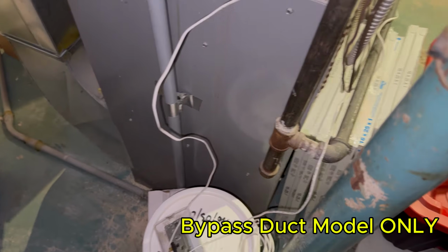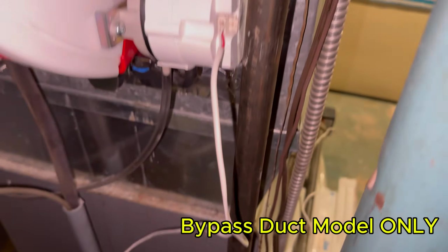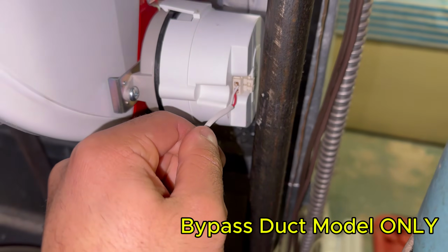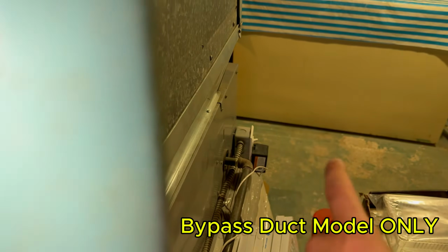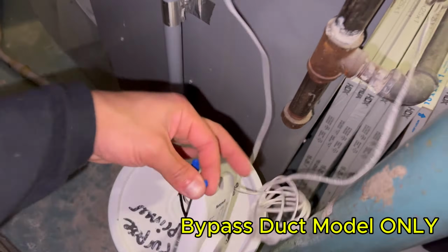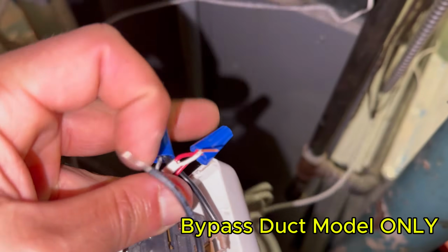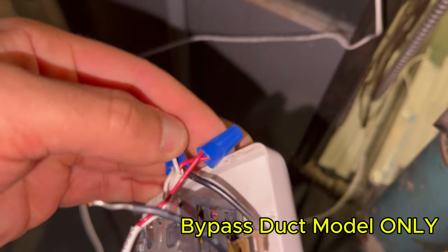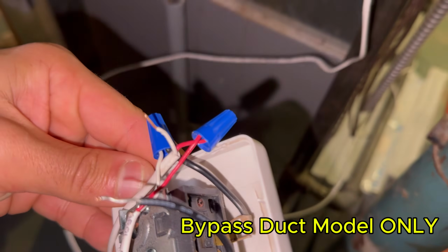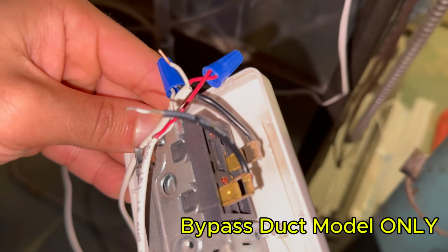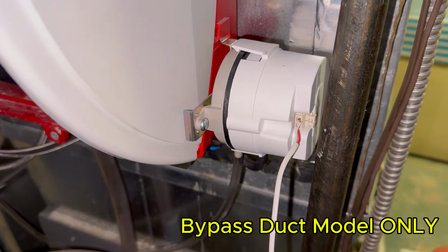Now, in order to wire this, you're going to take the red from the pressure switch and the red from the transformer and connect them together. So I've done that here. As you'll see, I've got 2 reds connected together. Those 2 reds, like I said, one comes from the pressure switch, the other from the transformer.